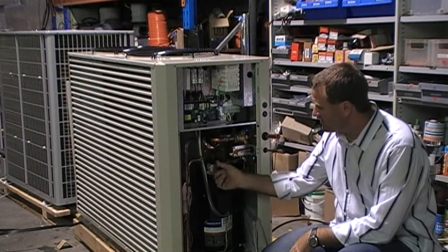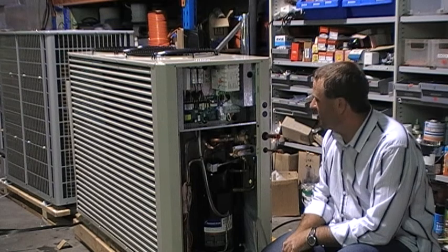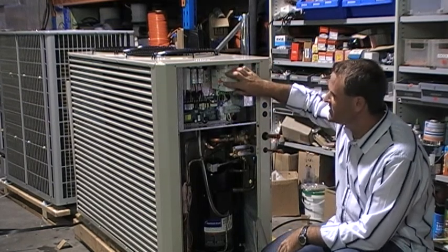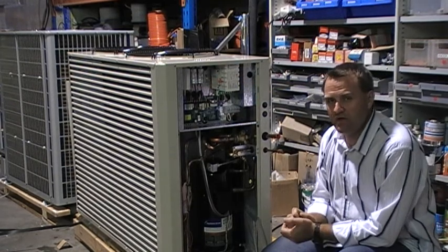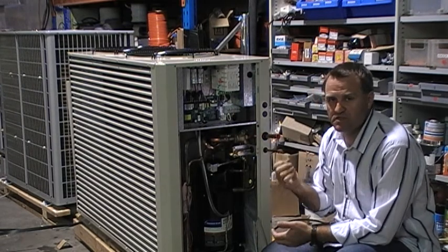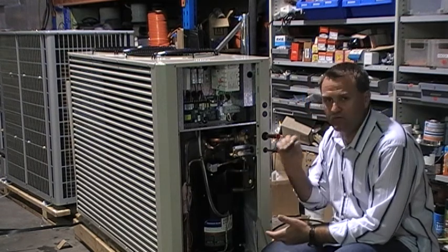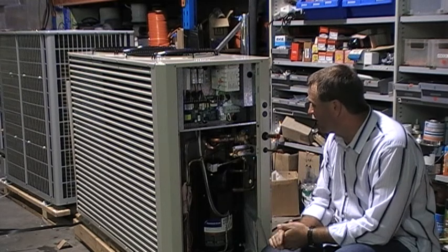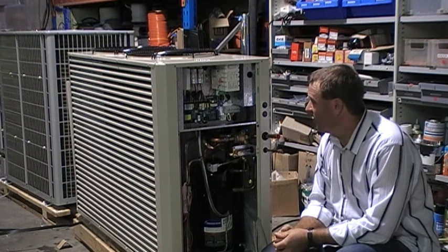Again, this is the loading and unloading solenoid valve on the Temperzone unit. The logic, they have a soft starter to stop your lights from dimming. Logic's in the board. The controller inside will tell the board at what algorithm to run the compressor at, and it will cycle on and off so many times per minute, which will give you the capacity that you require inside.